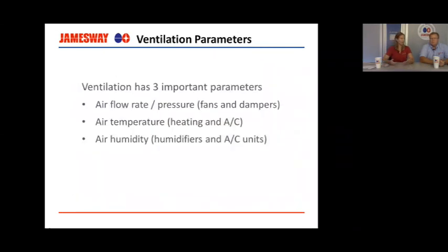So what is important in ventilation? There are 3 parameters. The first one is your airflow rate, which is also related to your pressure. It's controlled through fans and dampers. The next is the temperature, so either heated or air-conditioned chilled water coils, however you're controlling temperature, and then humidity. Humidifiers, AC units, dehumidification systems, whether that's on board on an AC unit or it's an inline electric duct heater in some areas of the world, or a hot water coil. All of those things contribute to dehumidification.